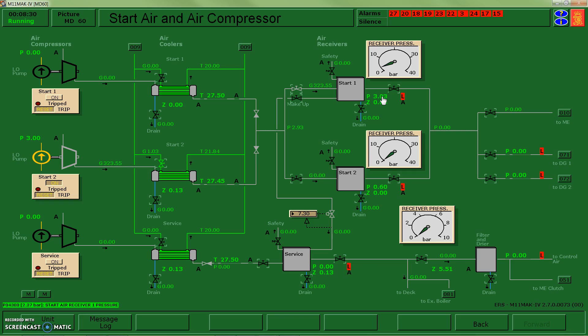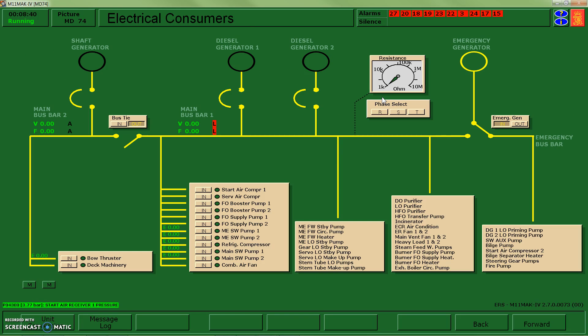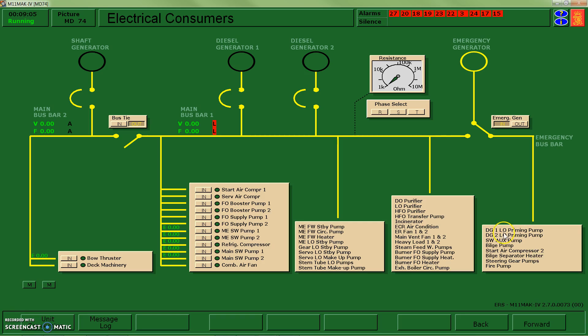Our next step is to start up the diesel generator. In order to get other systems going - like my service air compressor to feed power to my control valves - I need to get my diesel generators up and running, because they'll be able to supply enough power to run these systems. My next stage is going to be to use the compressed air from start air 2, my lube oil priming pumps, and my seawater auxiliary pump based off my emergency generator, in order to get my diesel generators running.